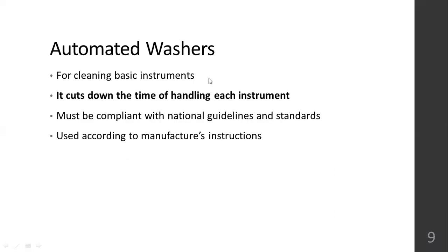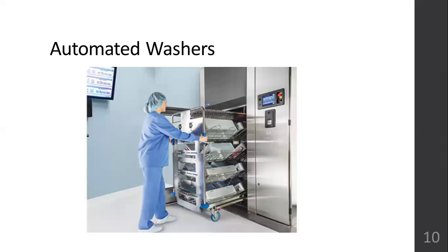Then we have automated washers for cleaning basic instruments. They cut down the time of handling each instrument, and whoever is using them must be compliant. The automatic washers which you have purchased should also be compliant with the national guidelines and standards, and used according to the manufacturer's instructions. This is how automated washers look like. They just make manual cleaning simpler. One by one, you don't have to clean the instrument. In one go, many instruments together can be cleaned, so it saves time, energy, and manual labor.